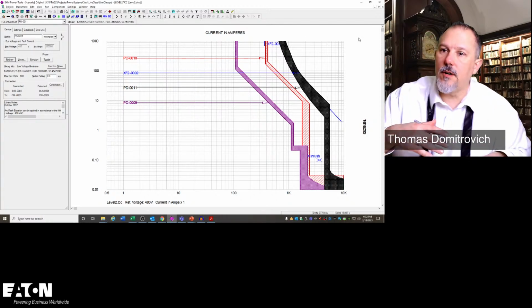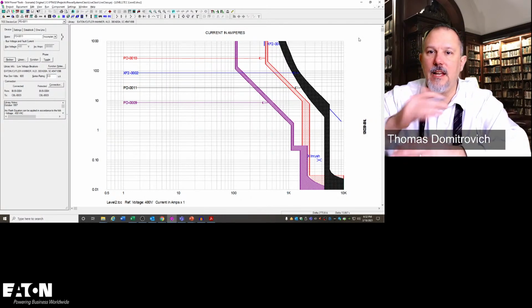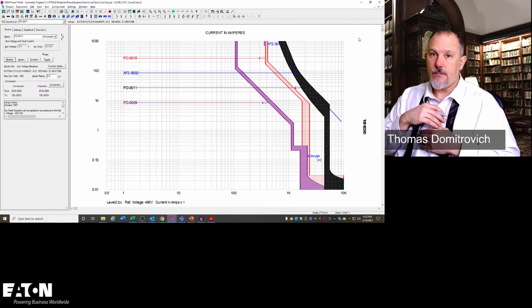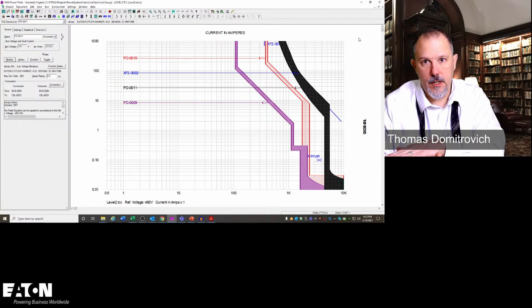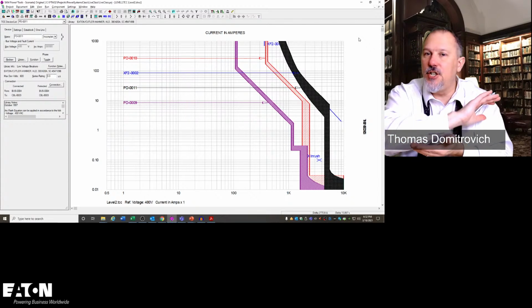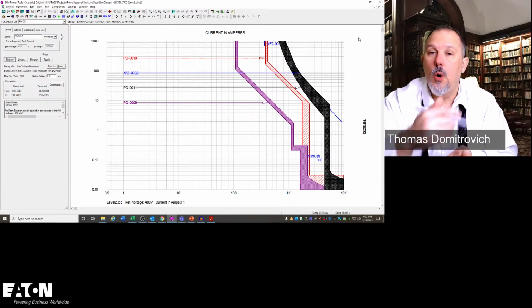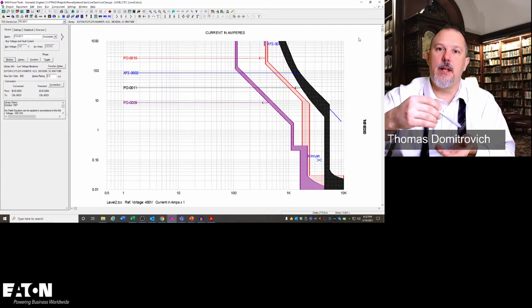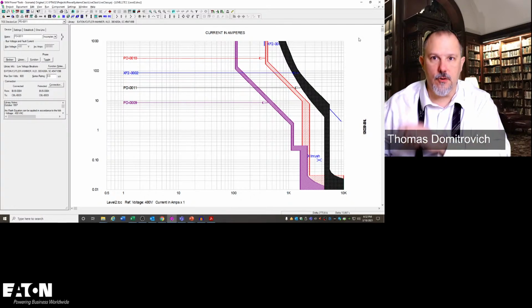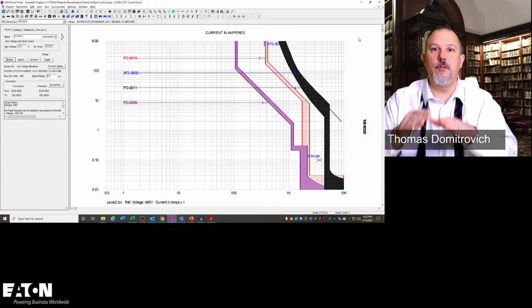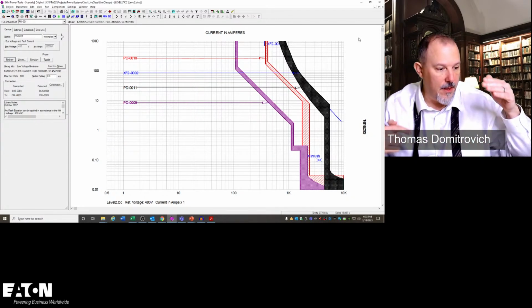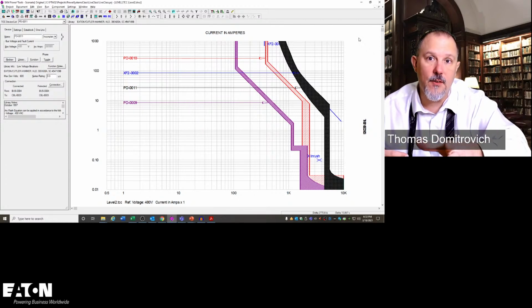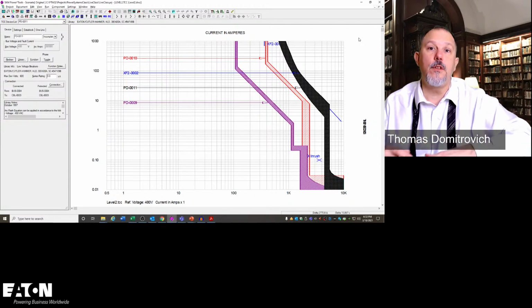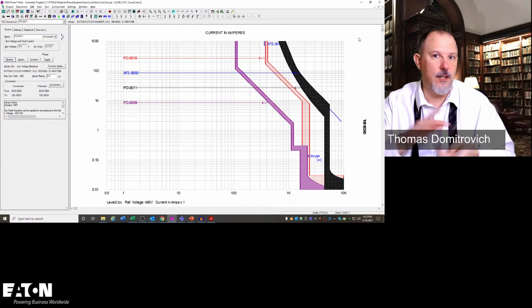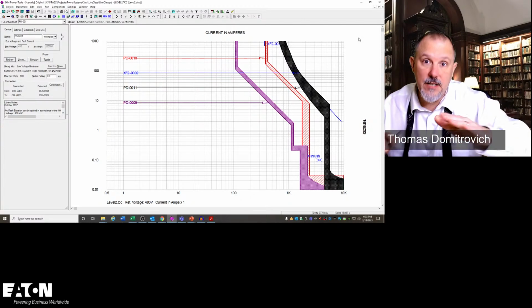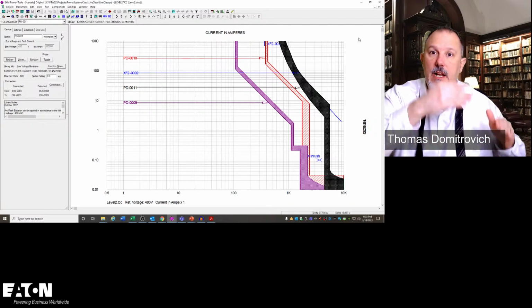Yeah, so MC, you could work it either way. What I did was I took the fault current and transposed it to the primary and didn't change the table values at all. Or you can multiply all of the table values by the turns ratio of the transformer, and then still use the secondary fault current, the 12,844. Whichever way feels comfortable for you, that's what you do. And that's the nice thing about math. You can skin a cat two different ways. So that's basically what happens when I'm selectively coordinating through a transformer.